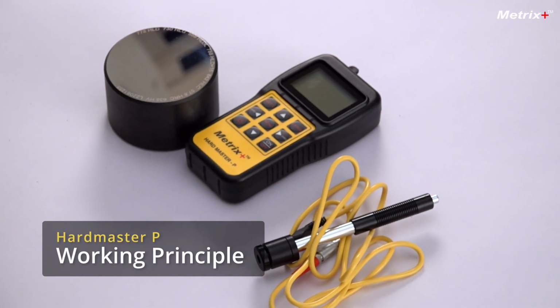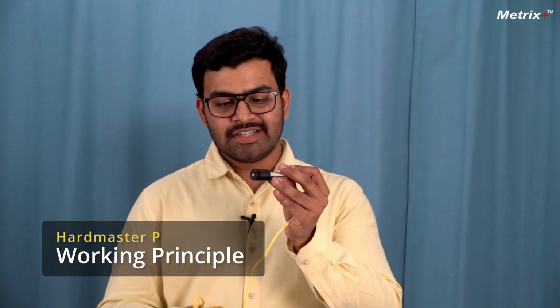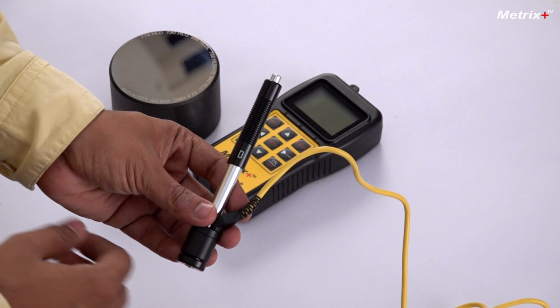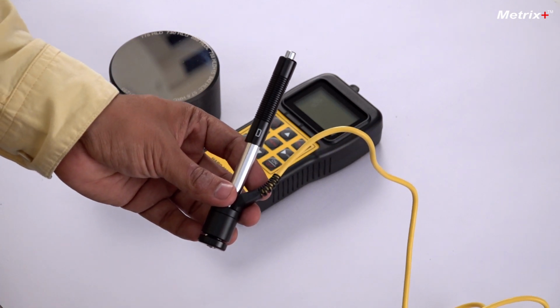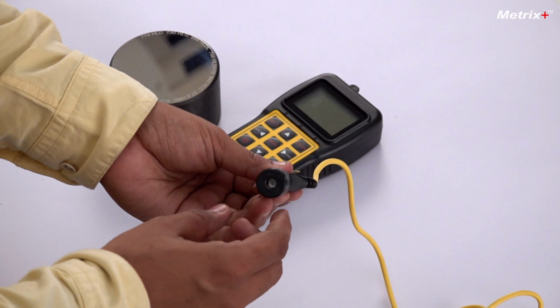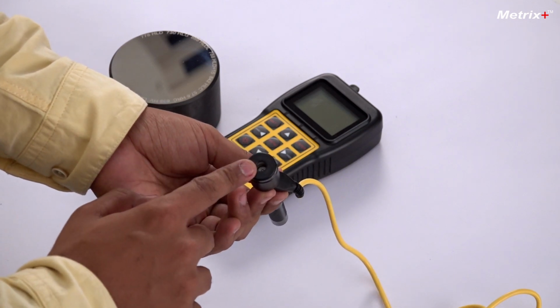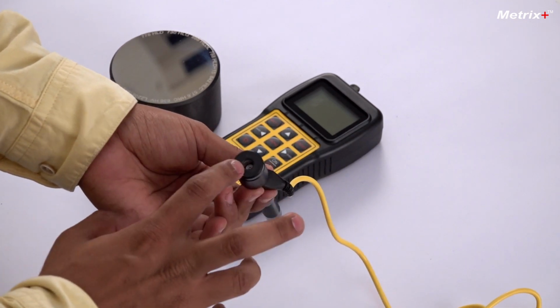Let's understand how this instrument works to measure the hardness. This is the probe. This houses the indenter inside. This indenter is of various materials. For common, D-type indenter is used. For thinner materials, C-type and so on and so forth. So right now we are using the D-type indenter and that is why the common measuring parameter will be HLD. How this works is the indenter first hits the material and then the rebound velocity is calculated to get the hardness value in common parameters.